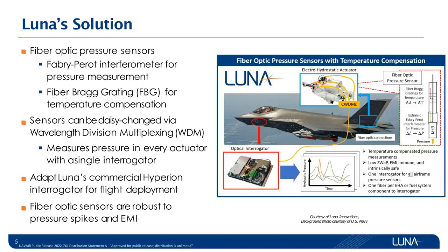Luna's solution is to combine two fiber optic sensing approaches to achieve robust and temperature-compensated pressure measurements. Fabry-Perot interferometers are extremely sensitive and are well suited to measuring pressure in extreme environments. However, they are typically also sensitive to temperature. Adding a fiber Bragg grating, or FBG, to the same sensing assembly allows for an independent measure of temperature and the ability to compensate the pressure sensor calibration for temperature effects.